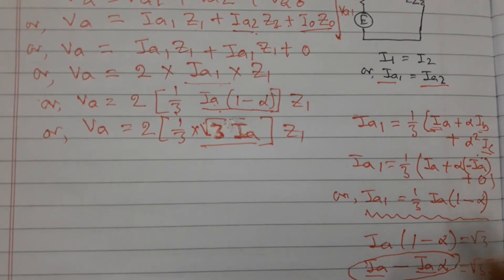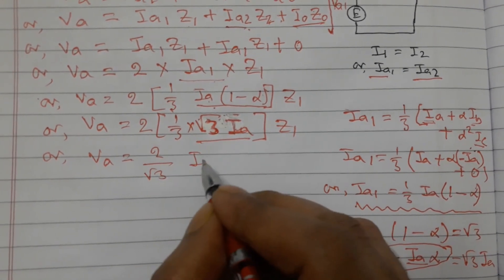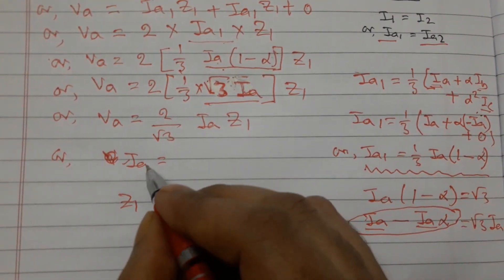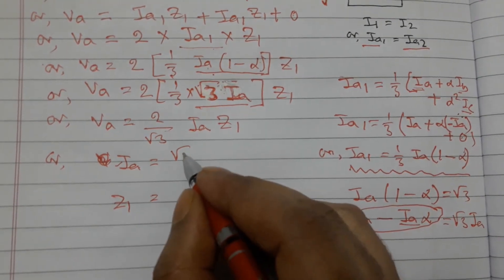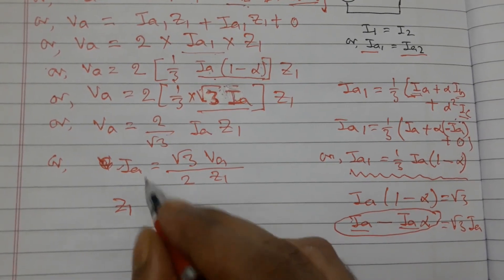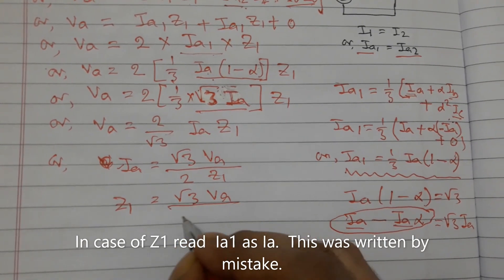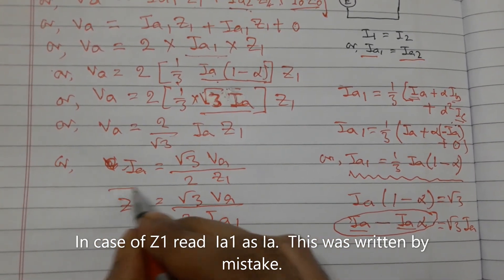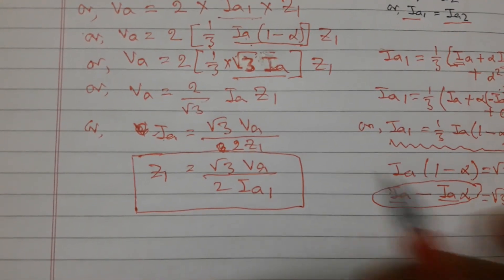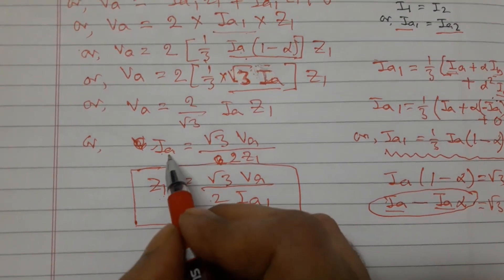Now we can write Va equals (2/root 3)·Ia·Z1. Rearranging, we get Ia equals root 3·Va divided by 2·Z1, and Z1 equals root 3·Va divided by 2·Ia. This is the impedance measured by the relay — the value of Z1 that the distance protection relay sees — and Ia is the fault current flowing through the fault loop.